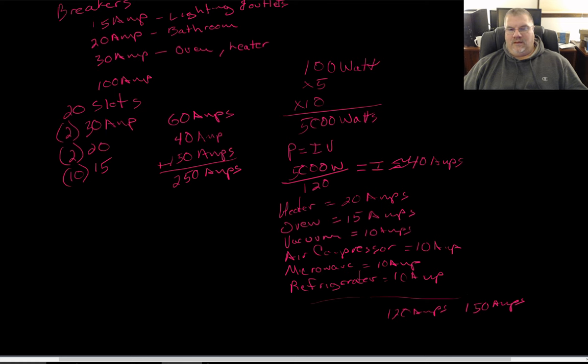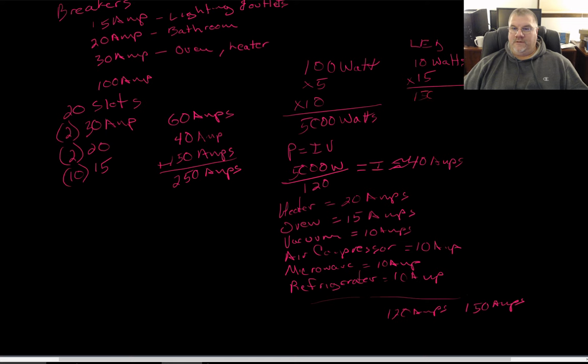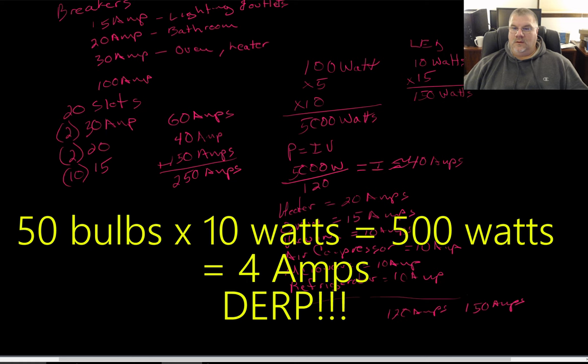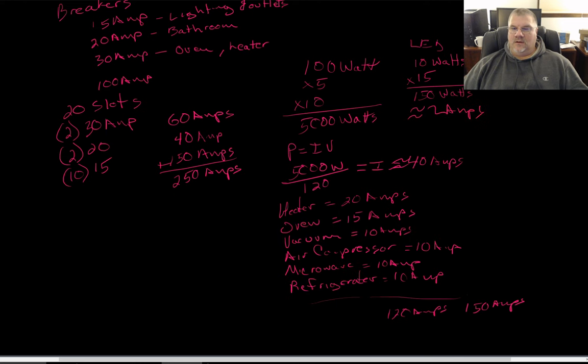Now with LED lighting: instead of 100-watt incandescent bulbs, LEDs pull about 10 watts each. With 15 bulbs that's only 150 watts — divided by 120 volts, that's less than 2 amps, compared to the 40 amps for incandescent. That alone reduces our running load significantly. So instead of 120 amps we'd be down closer to around 80 amps — well within our 150-amp service.